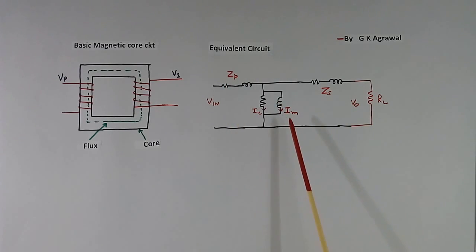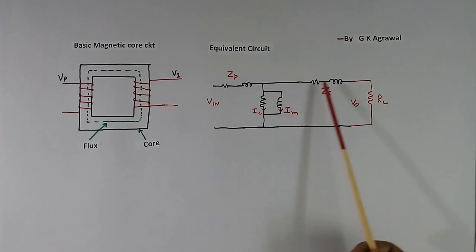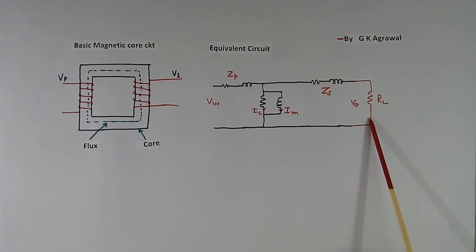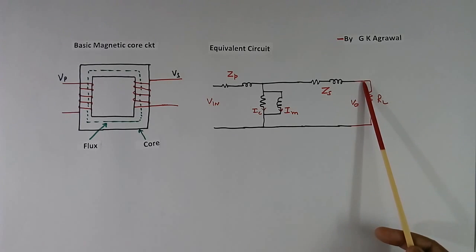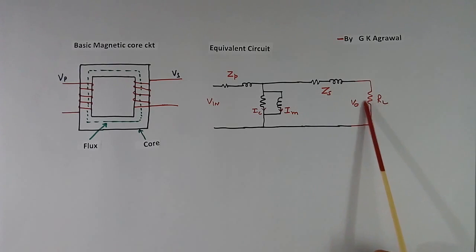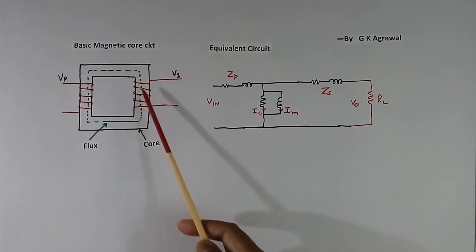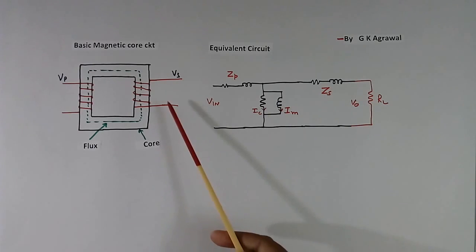This is the equivalent circuit of the PT. Here I have clubbed the two separate windings together. This shows the core loss, this is the magnetizing current, this is the primary impedance, and this is the secondary impedance. Because of these two impedances, when we connect a load, a current flows and there will be a voltage drop. If the load is resistive or inductive, voltage will be less. To compensate for that, the PT manufacturer will provide additional turns — suppose by calculation 100 turns are required, they will make 101, 102, or 103 — to compensate this drop and bring accuracy to the PT.